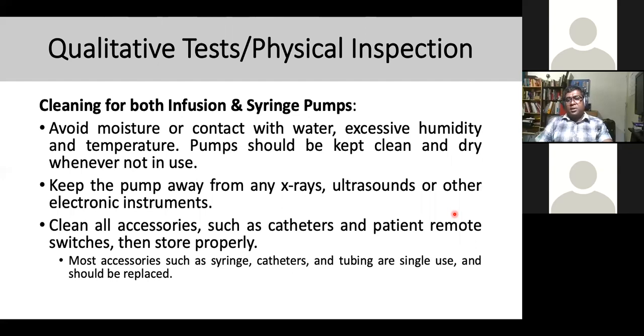So when you talk about qualitative tests, physical inspection, cleaning for both infusion and syringe pump: avoid moisture or contact with the water. Always keep dry and clean the screen, all that properly. And keep the pump away from X-ray, ultrasound, and other electronic instruments. Clean all the accessories such as catheter and patient remote switch and store properly. Most of the accessories like syringe, catheter line, tubing are single use, except the switching. So this particular thing is a single use thing.